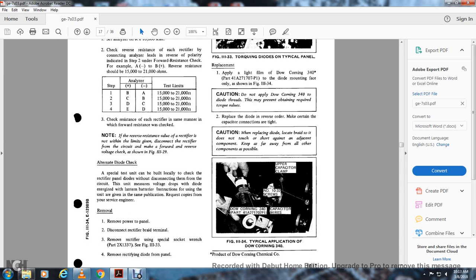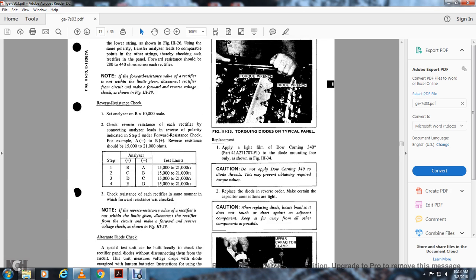Alternate diode check. A special test unit can be built to check the rectifier panel and diodes disconnected from the circuit. The unit measures the voltage drop of the diode energized with the lantern battery. Instructions for the unit are given in the same publication, available from your service engineer. Step 4: remove the power panel and disconnect the rectifier braid terminal. Remove the rectifier using the special wrench, figure III-33. Remove the rectifying diode from the panel.